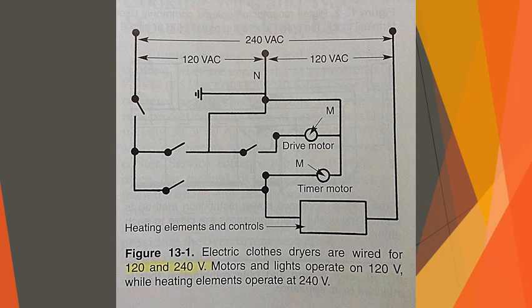General considerations. A separate appliance circuit may be designed and connected to supply both 120 and 240 volts for devices such as electric ranges and clothes dryers. These appliances may have different voltage needs at certain times during their operation. For example, clothes dryer circuits are varied and may be split so that high heat is supplied at 240 volts while low heat is supplied at 120 volts. Figure 13-1 is a schematic for such a circuit.